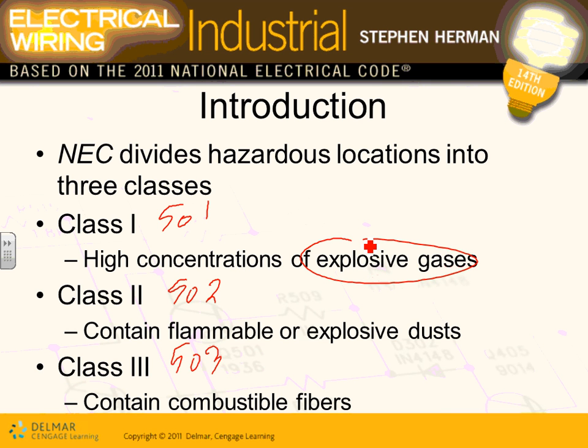Your gas station, your petroleum refineries, any place where you have gases that can ignite and explode. Natural gas, all types of petroleum products, most petroleum products will fall under explosive gases. So any place where you manufacture, process or deliver these gases has to be classified as Class 1. Any questions, guys, about Class 1 locations, explosive and flammable gases and vapors? Does everybody understand that one? Any location that has vapor, gas or even liquid that can be explosive, flammable, ignite and explode is classified as Class 1.